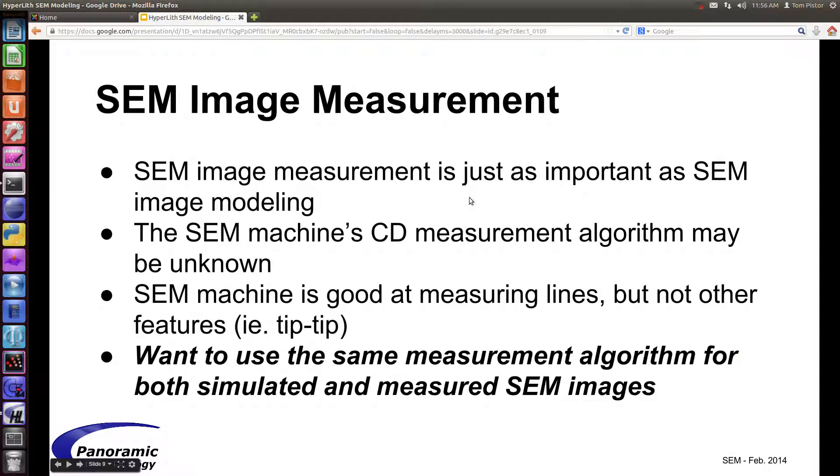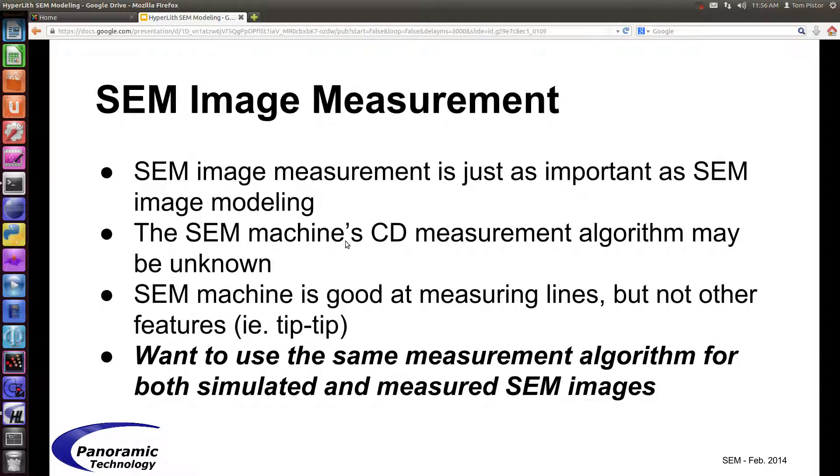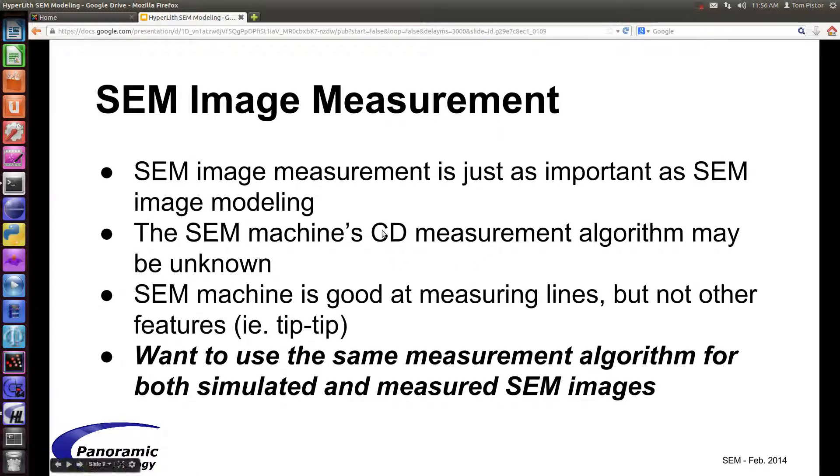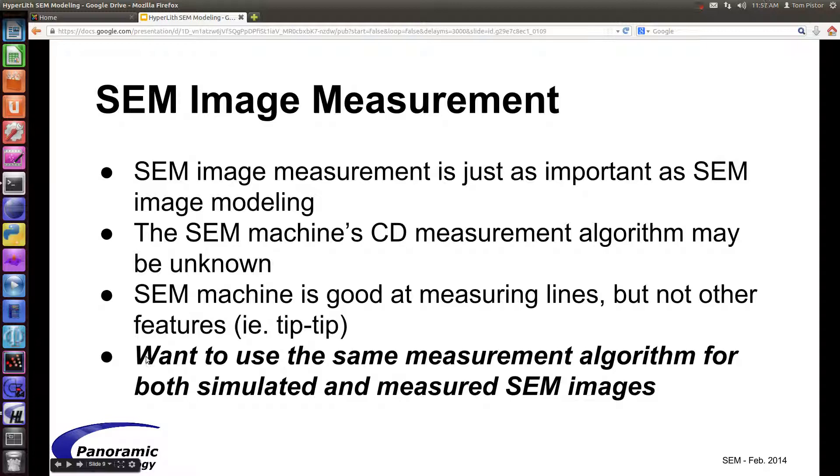I'll skip to the part of the presentation where we're talking about SEM image measurement. The measurement can be just as important as the SEM image modeling itself. This is because the SEM machine, when it makes a measurement, uses an algorithm that does some smoothing, and it may not be known to the user what the measurement algorithm is. It may decide that the edge is in a different place than you might decide if you looked at a SEM image with your eye. Also, the SEM machine isn't very good at doing other types of fancy measurements, for example, a measurement of a contact or a line end or a tip to end or a tip to tip.